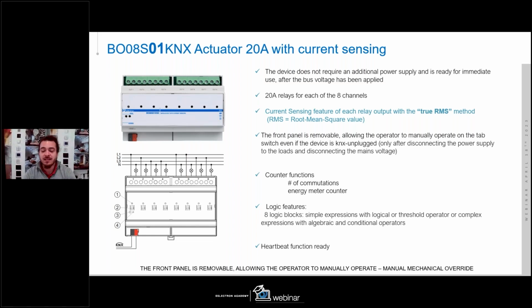BO08S01 KNX. That is still a 20 amps relay actuator, always 8 channel output, and everything that we saw before is present also in this version. In this case, we add the opportunity to not calculate, but measure the real active power and consumption of the output. This is because inside each output there is a current sensing feature with a true RMS method. RMS stands for root mean square value. And thanks to this hardware, we can not count but measure the real consumption of the output. So we can say how much is the active power of the output or how much energy we use with this output. Everything that I said before is still present in this module.